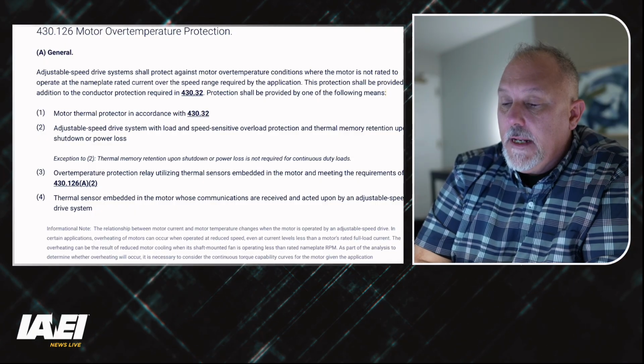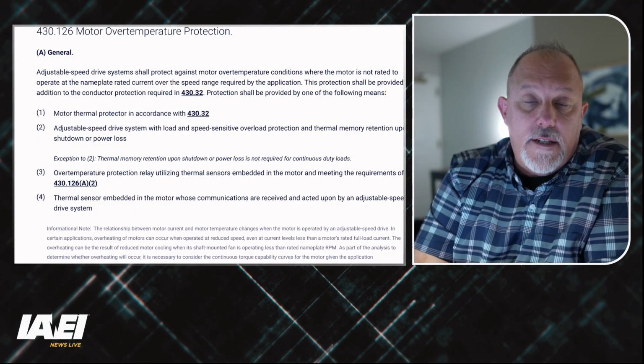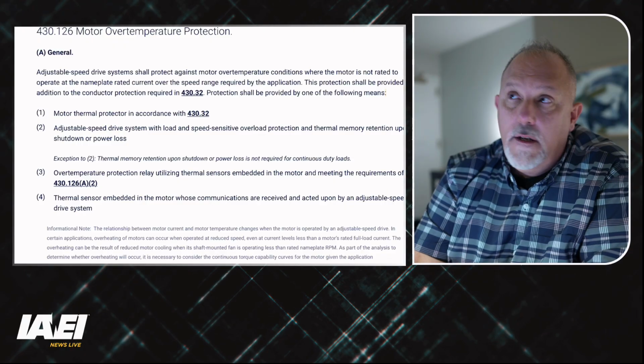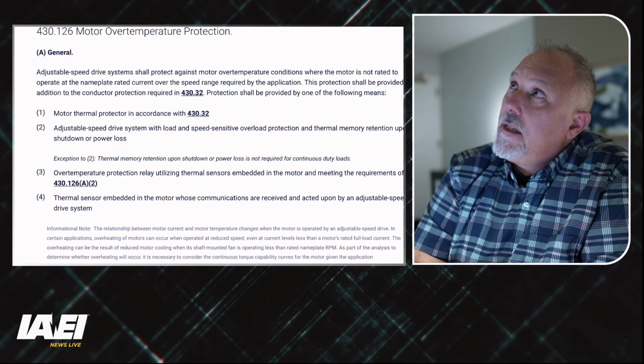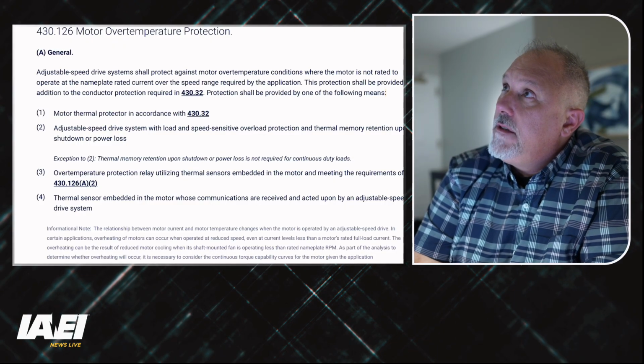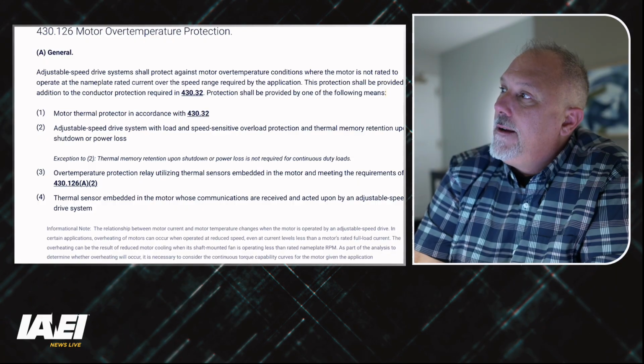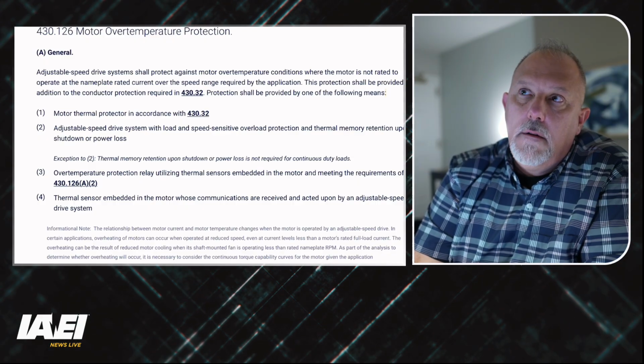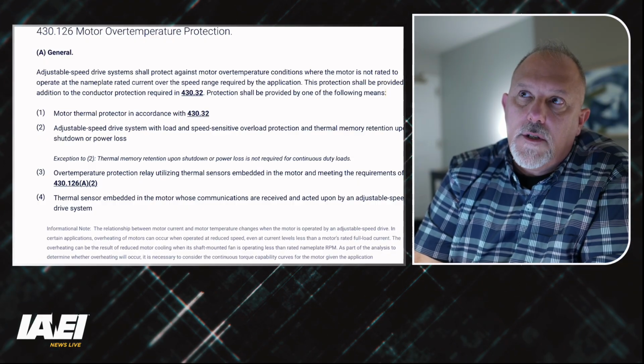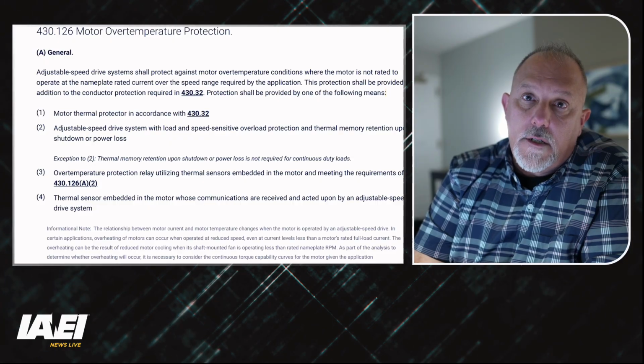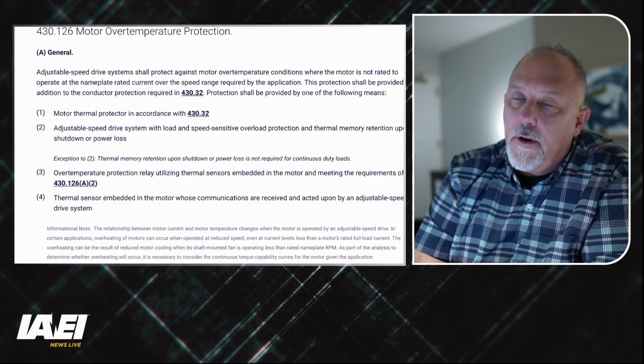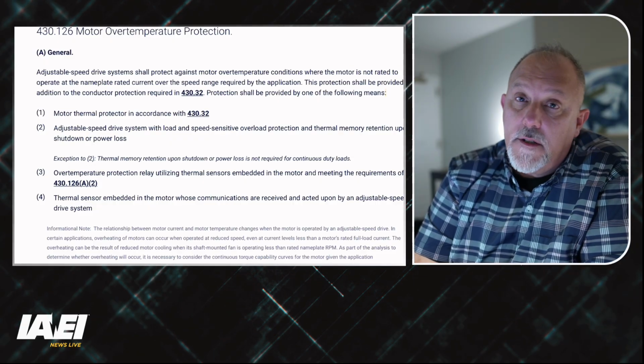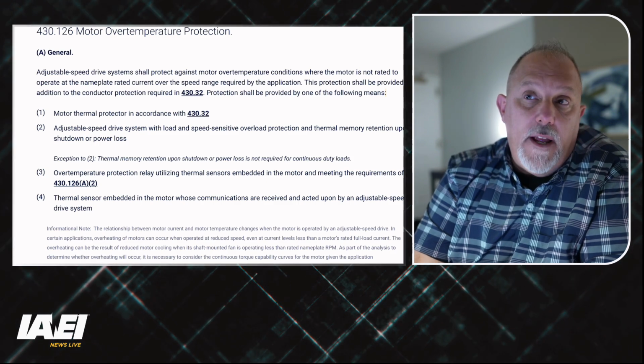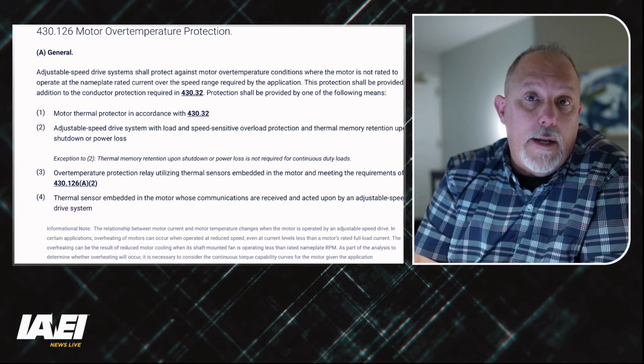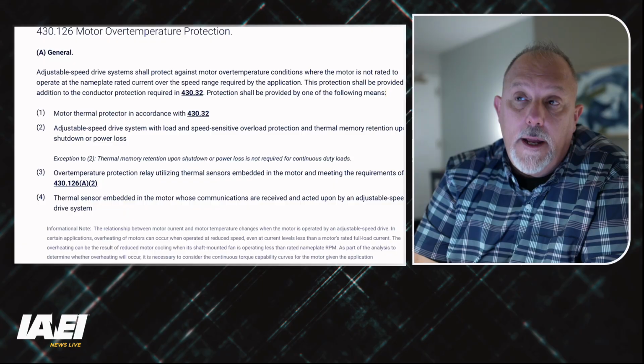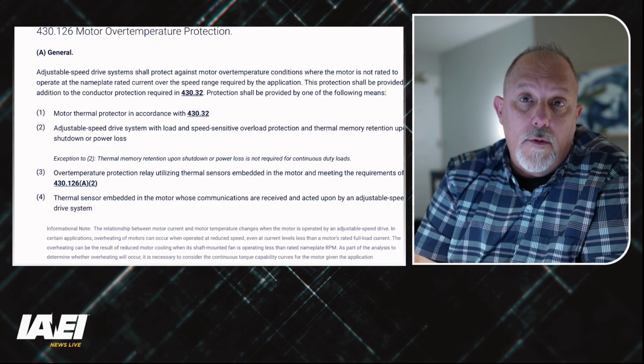Over temperature protection relay utilizing thermal sensors. That's your RTDs. What was that? Resistance thermal detectors? Can't remember, but basically the way an RTD functions is as it gets warmer, it changes the resistance. So you monitor that resistance and it tells you what the temperature is. And then you alarm on it. And you may have a motor relay that is pretty daggone complicated and takes into consideration the thermal capabilities.